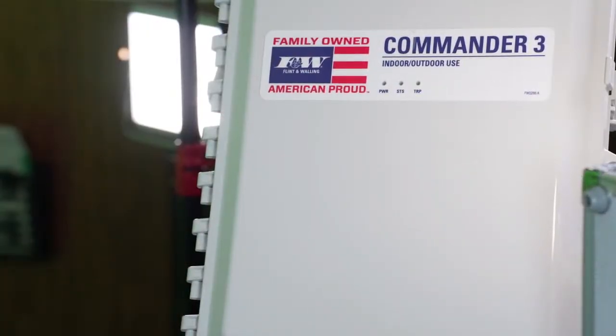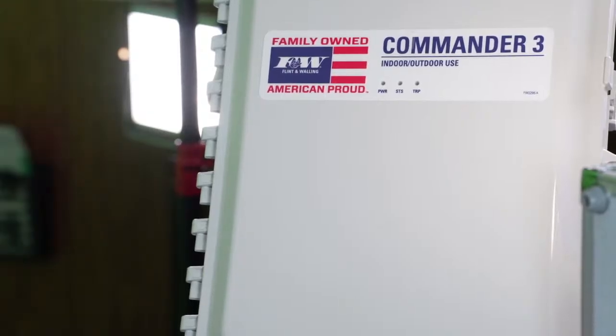Basically what that's going to do on the cover is give us an indication of the power, the status, and any type of trip that this drive may see. It'll indicate that also on the front side of this drive. So that green light, the first one, is the power light. When it's illuminated, that'll be a solid green. That's just going to indicate that you've got the controller powered up.